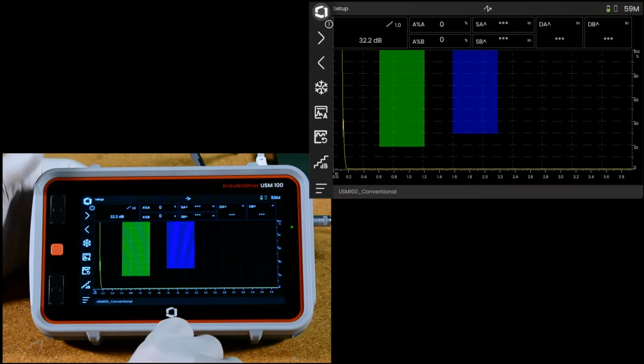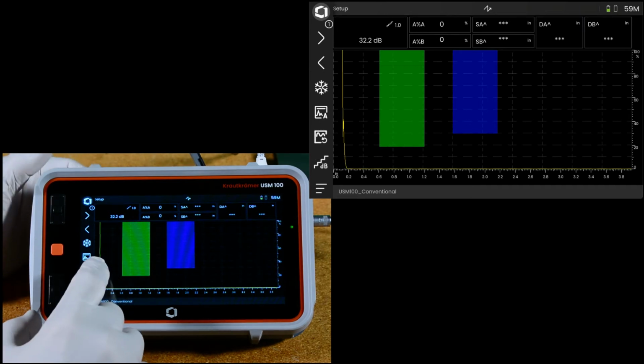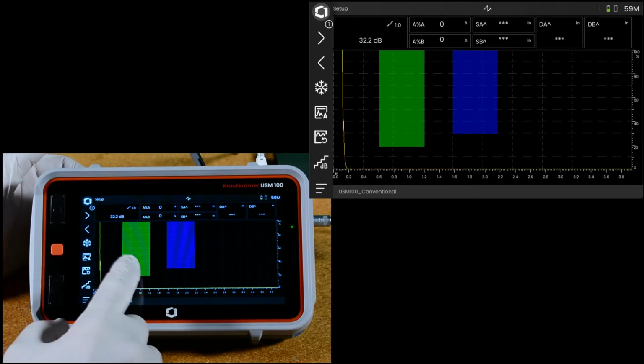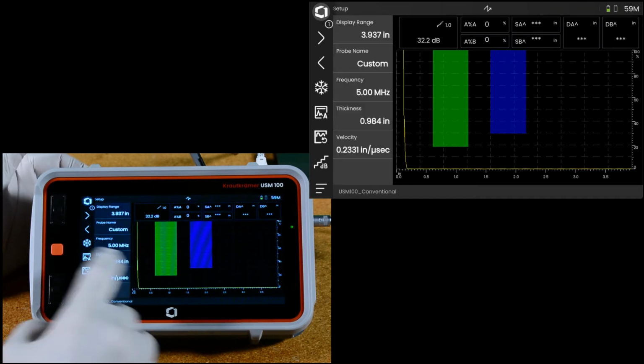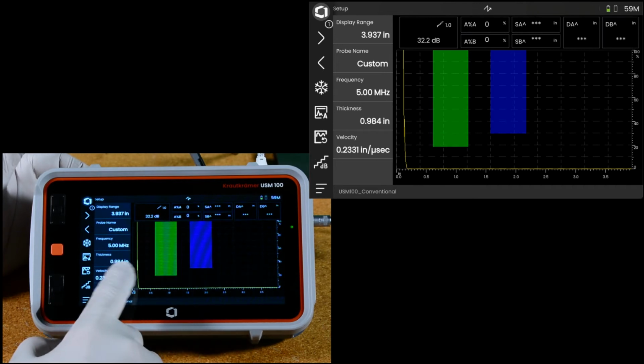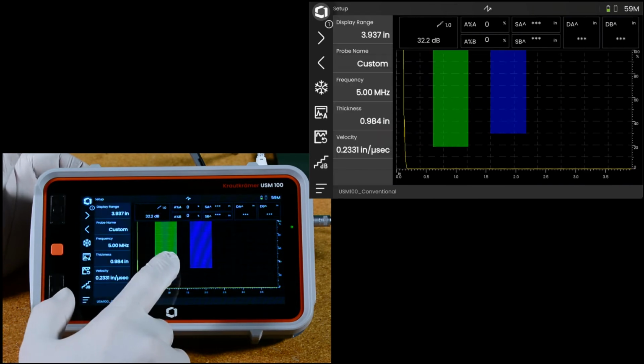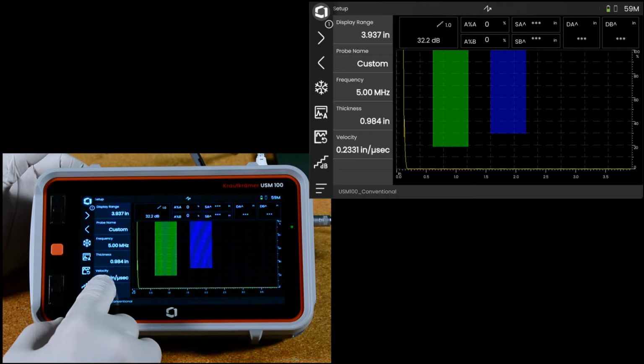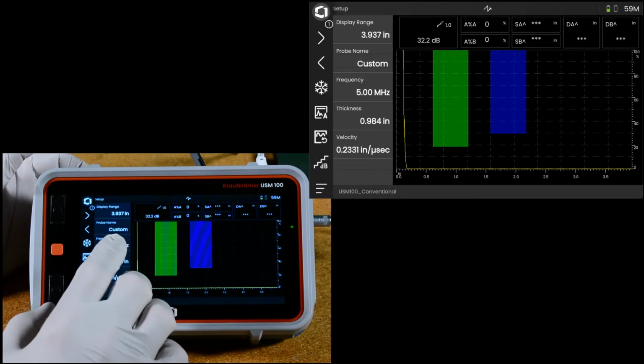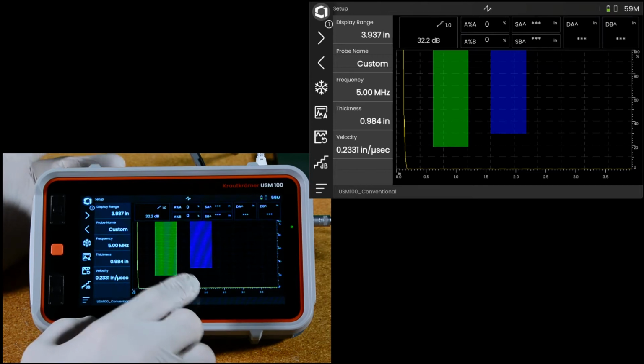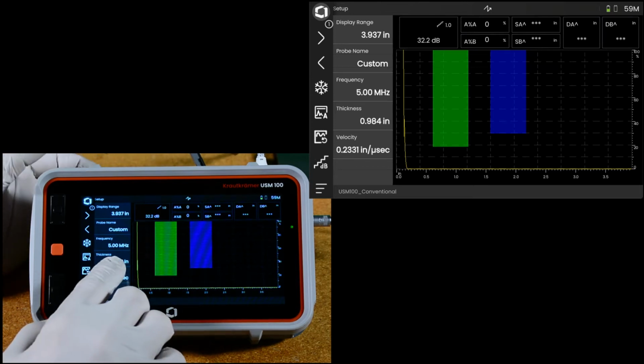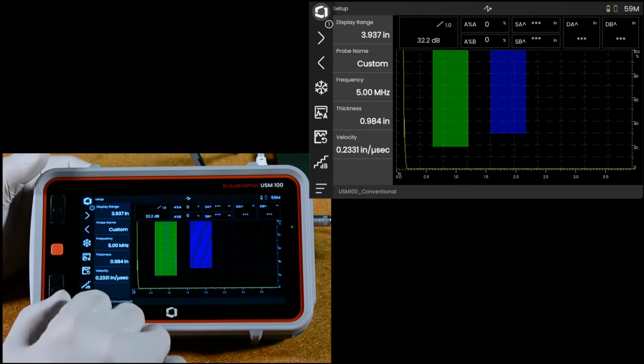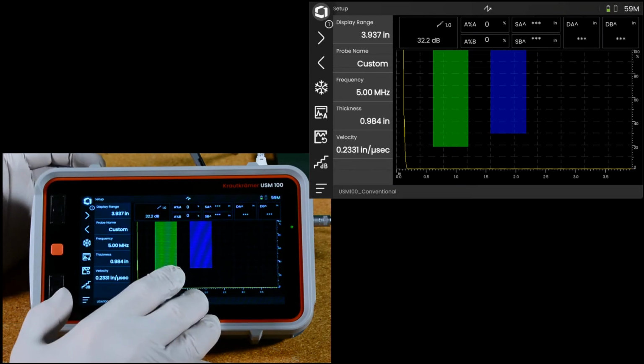Okay. The next feature of the instrument is that each panel of the app will have a special sidebar menu. The sidebar is accessed by pressing here at the left edge of the A scan and swiping your finger to the right. The sidebar is put away by just putting your finger down somewhere in the sidebar and swiping it back to the left. So swipe it out, and you get a menu that is custom for each one of the panels of an app. There are some default menus based on the panel type, whether it's calibration, inspection, what have you. Or the app author can add controls to this or hide controls, whatever makes sense for the app.